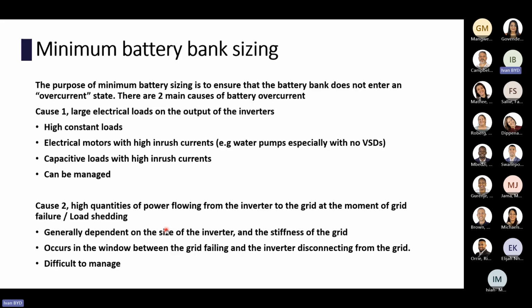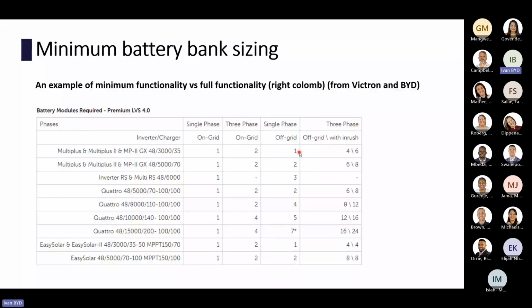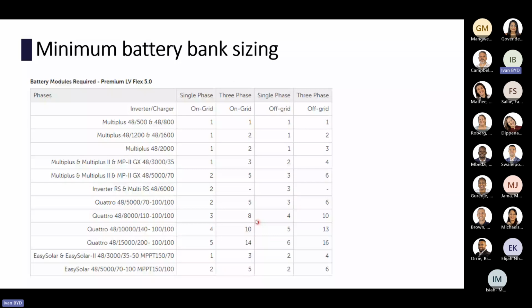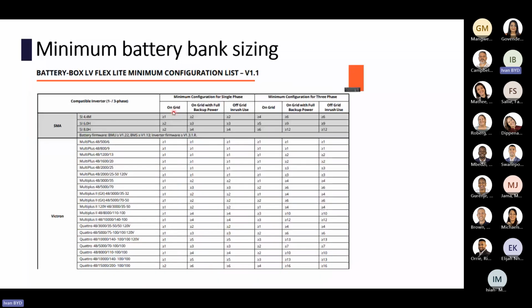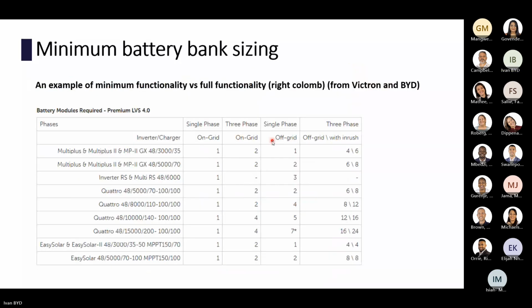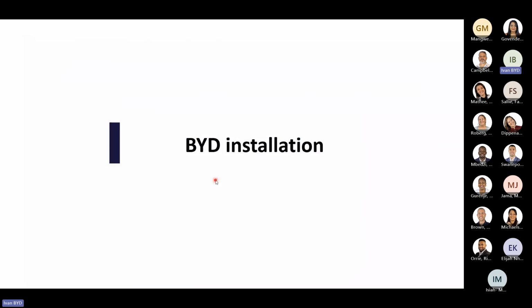Here are some examples of the minimum battery bank sizing. And here's an example of the Victron BYD site. Some more examples of those stats. The on-grid is designed for Europe, where they've got a stable grid and no backup. So please don't use the on-grid recommendations for South Africa. They're designed more for Europe: no backup, stable grid. Same for the Victron guides.